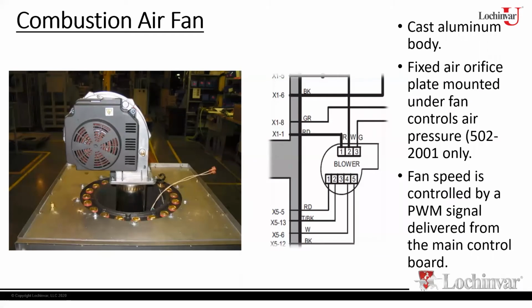Now, with that said, if you've got anything that's pulsing power to the control module, such as some sort of safety switch, a flow switch, a block drain switch, an air switch, or some other remote device like a tank thermostat, and we have run into this before, if you're basically telling the module start, stop, start, stop constantly, that's telling the fan to do the same thing. And that fan is going to try to ramp up, down, up, down. And eventually the module is going to say no more, and you're going to go into a lockout.